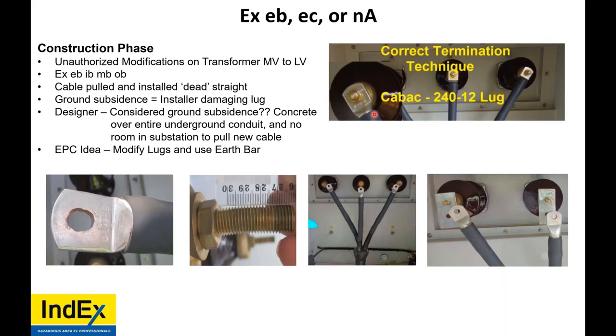But what they did do is, due to the subsidence, the stud was damaged. So the EPC came up with the idea to elongate and modify the lug holes to make it fit. But when they put it on, they bent it. So when they were too short, they then took an earth bar and cut it down.